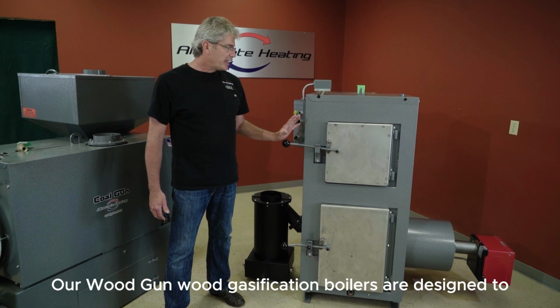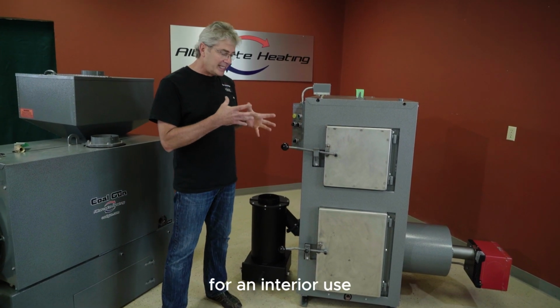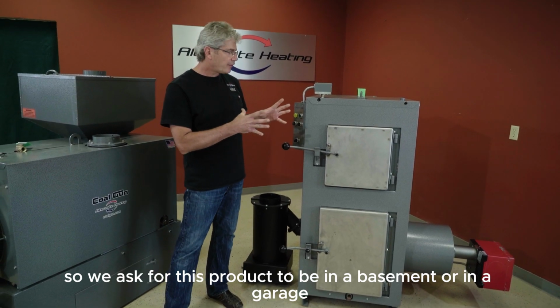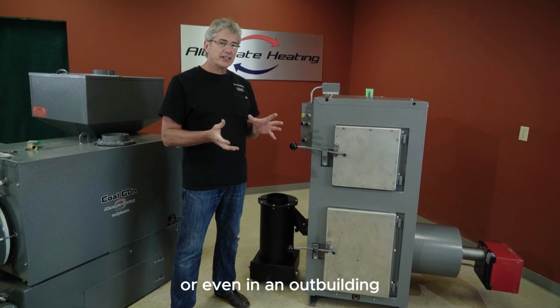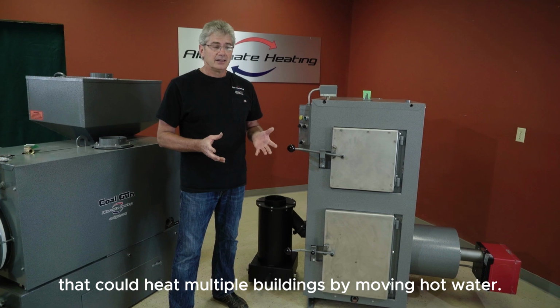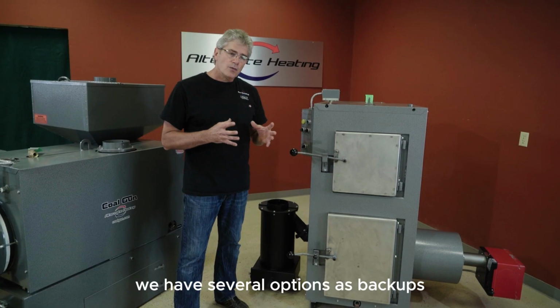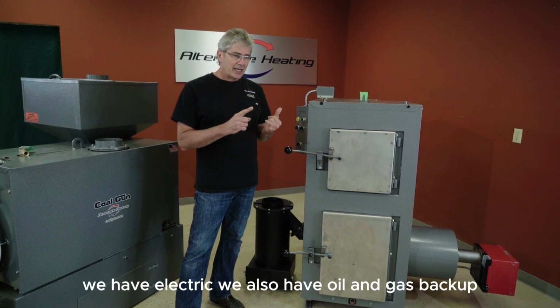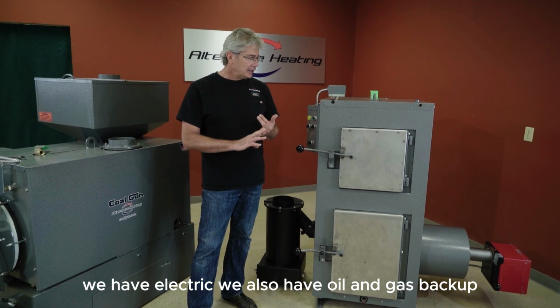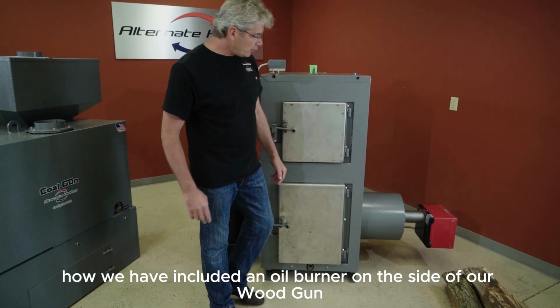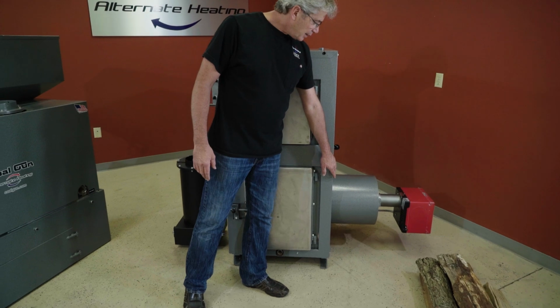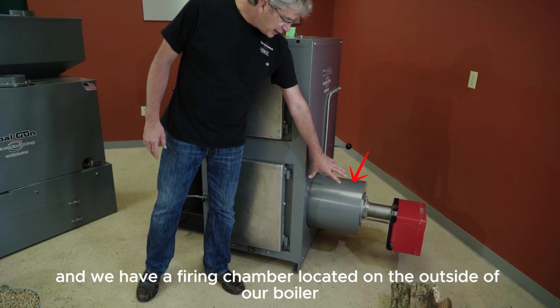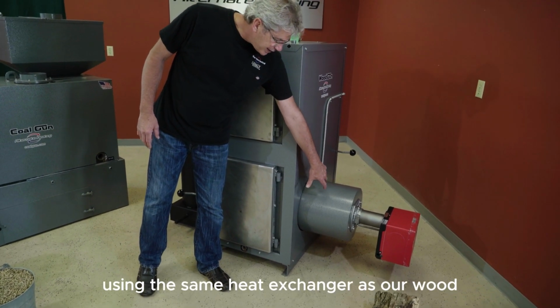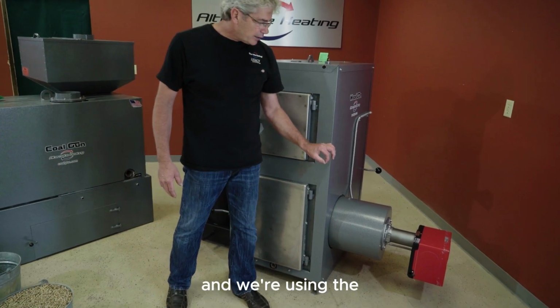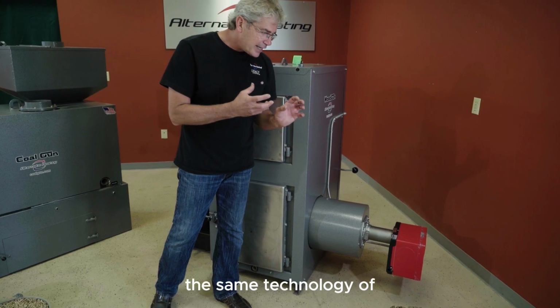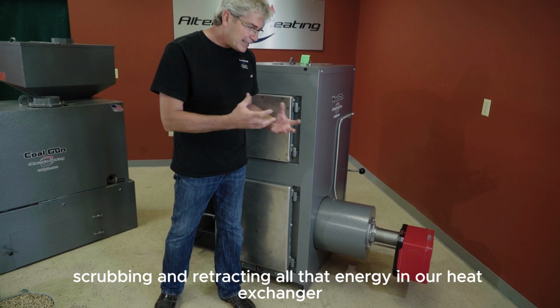Our wood gasification boilers are designed for interior use. So we ask for this product to be in a basement or in a garage, or even in an outbuilding that could heat multiple buildings by moving hot water. We have several options as backups. We have electric. We also have oil and gas backup. You can see here how we have included an oil burner on the side of our wood gun, and we have a firing chamber located on the outside of our boiler using the same heat exchanger as our wood, and we're using the same technology of scrubbing and extracting all that energy in our heat exchanger.